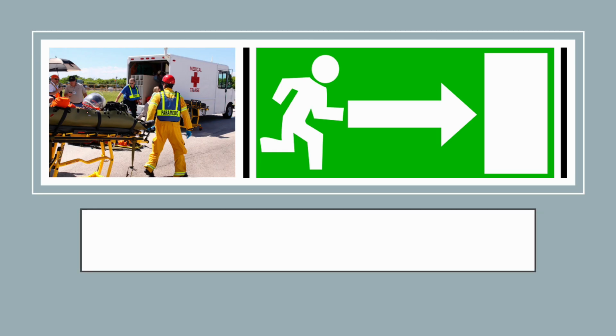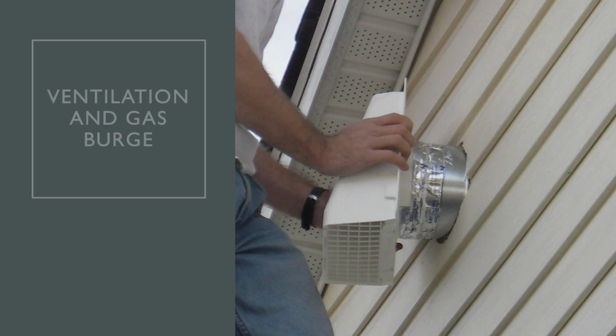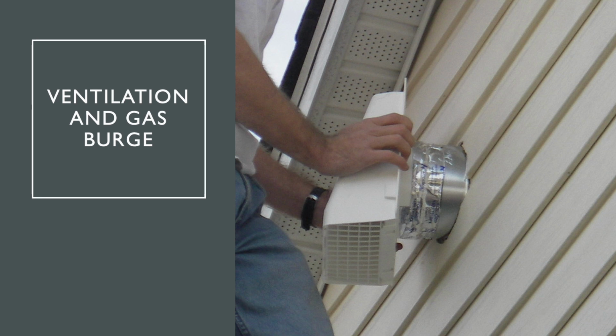The second measure is to evacuate. Departments should establish an evacuation plan in advance and ensure that all personnel are familiar with the escape routes and assembly points. Evacuate the area immediately, following the predetermined evacuation plan to a safe location outside the affected zone. Third is ventilation and gas purge. In some cases, superconducting systems may require gas purging or ventilation during normal operation. During a quench, ensure that adequate ventilation systems are activated to remove any hazardous gases, such as cryogens or coolant vapors, from the area.